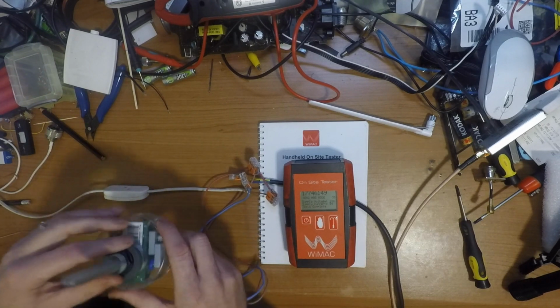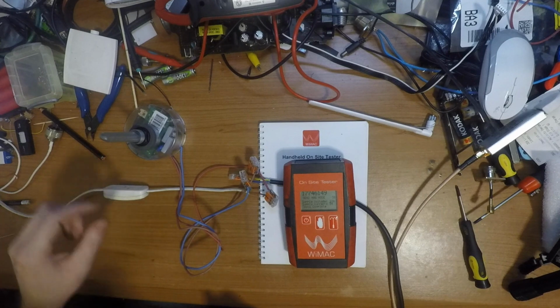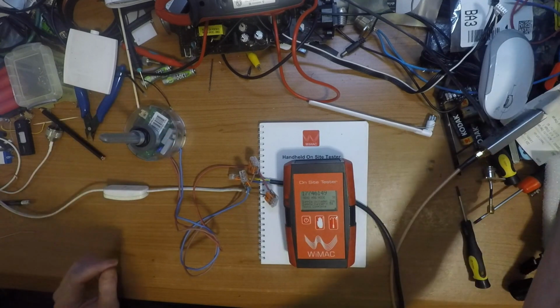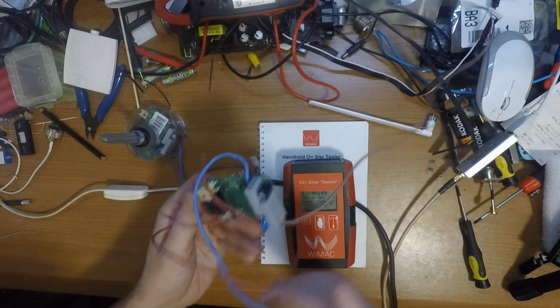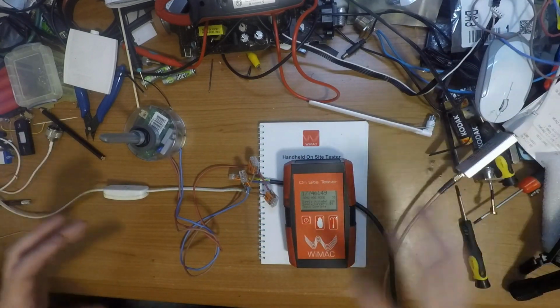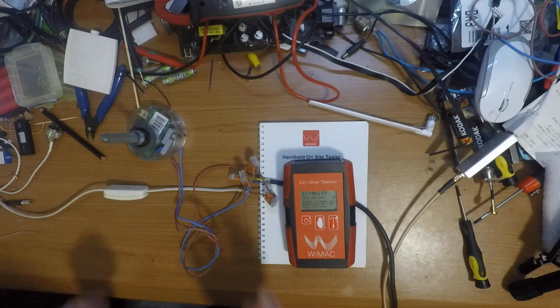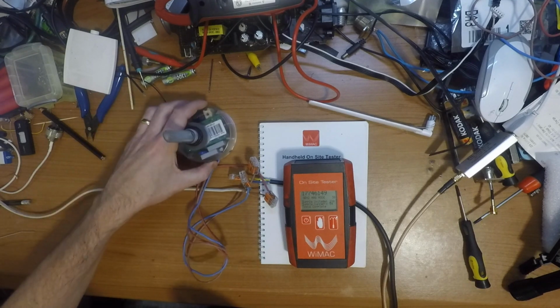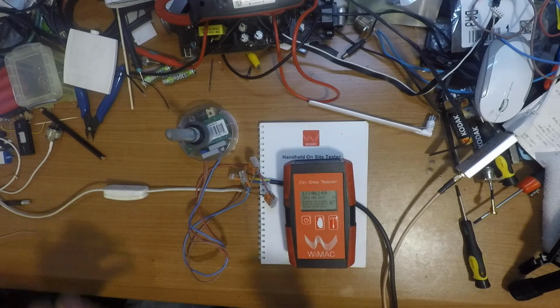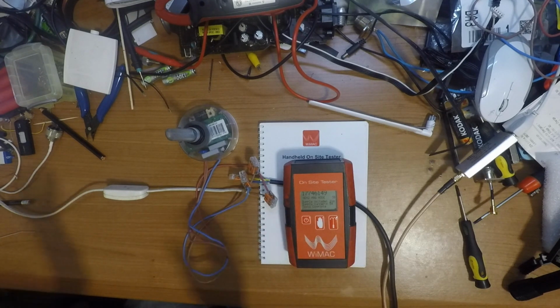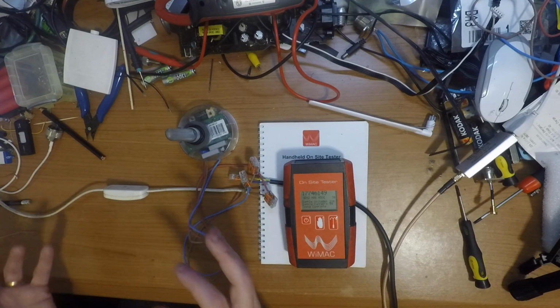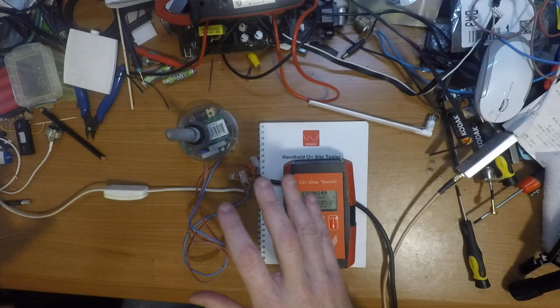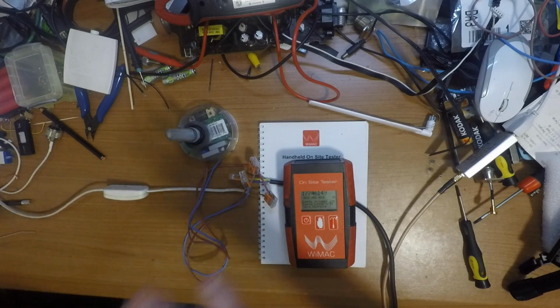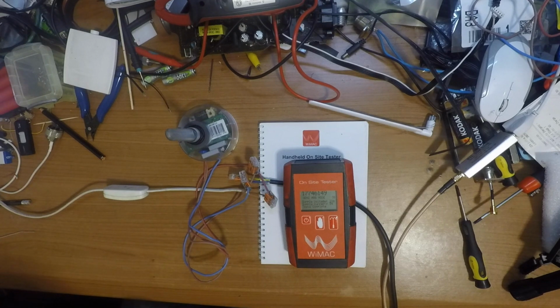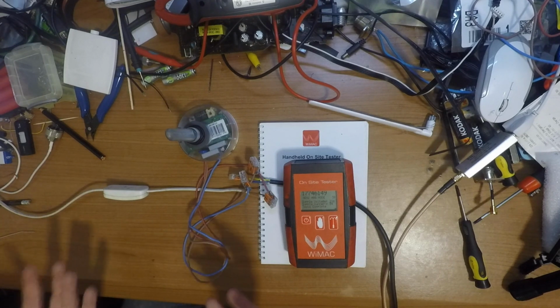The other version of this is a little black box, and it's smaller because it hasn't got this main switching circuitry in here, because it is designed to control the power supply for an LED light. And they are a bit more interesting because they can not only turn the lights off and on, they can also dim them. So if you combine dimming with presence detection, you have lights that are on but dimmed all the time, and they only go on to full brightness when somebody is either walking in the alleyway or the pavement, or vehicles are using the road. And Mark actually has some videos that show that.